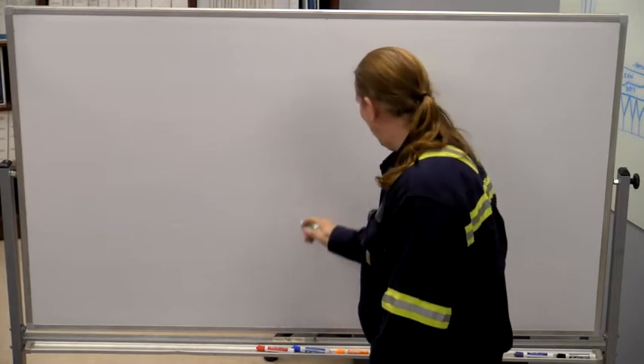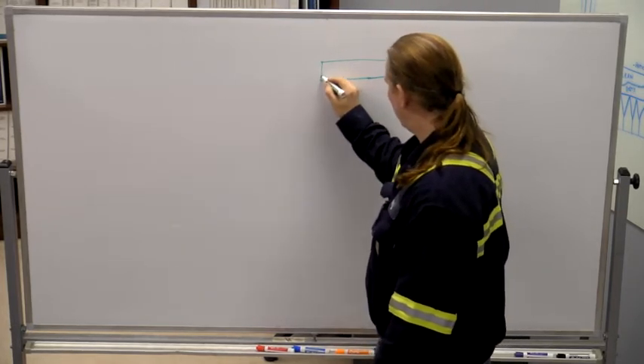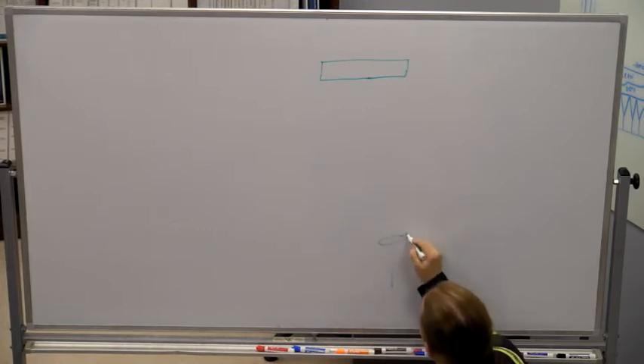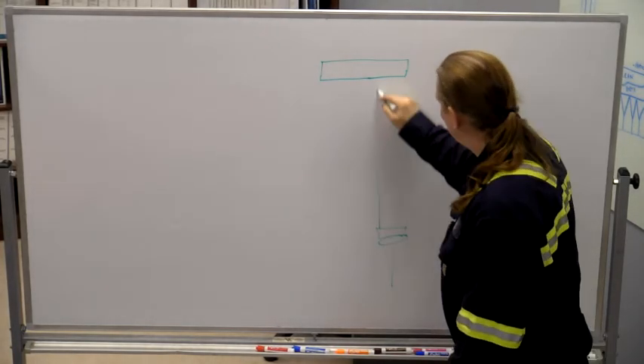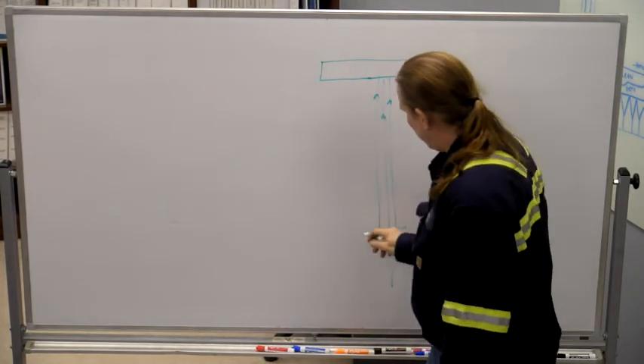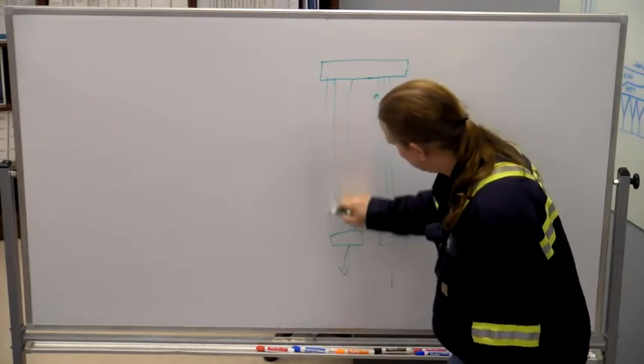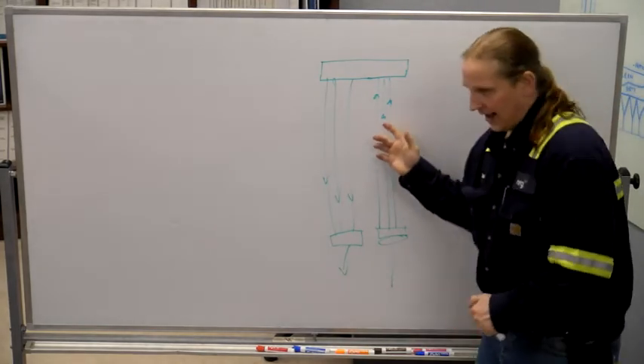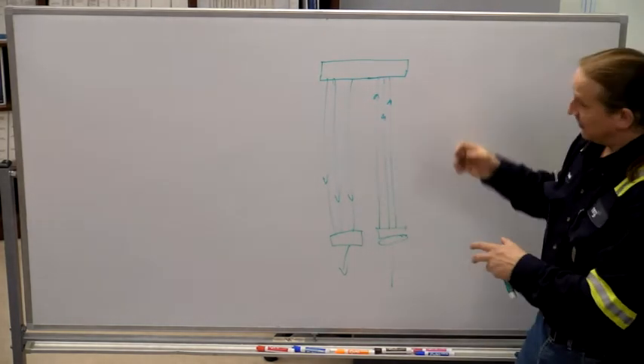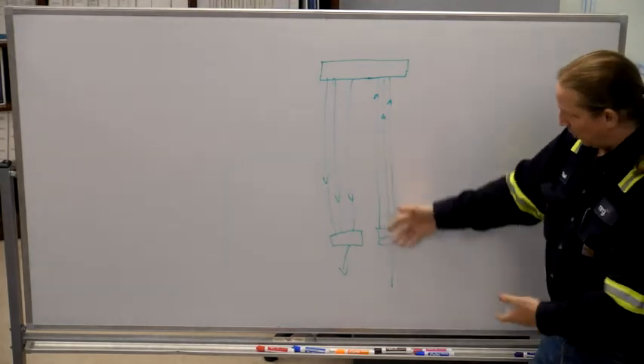So this cooler, zooming in on the cooler. So what you've got is an inlet pipe, and then that goes to a water box, and then that goes to 700 little pipes. And then you have an outlet water box. You've got 700 more little pipes going the opposite direction. And then all of this has that air conditioner type fill, the little aluminum zigzags that just create more surface area so that the hydrogen interacts with it more, because surface area is key to heat transfer.